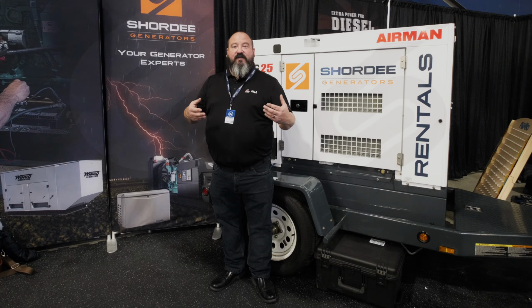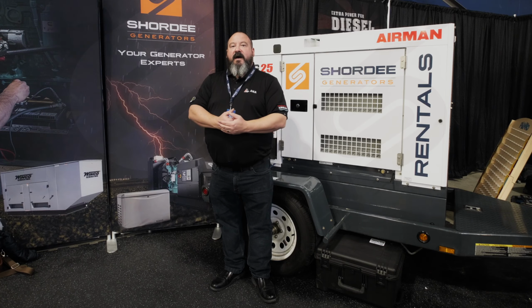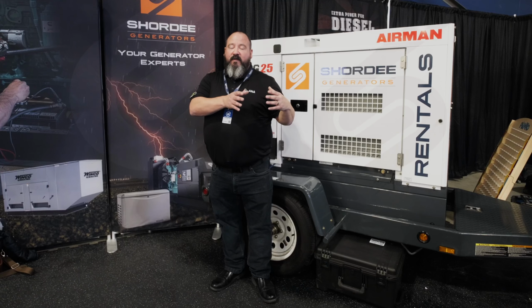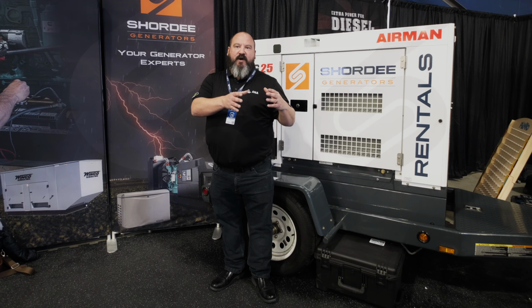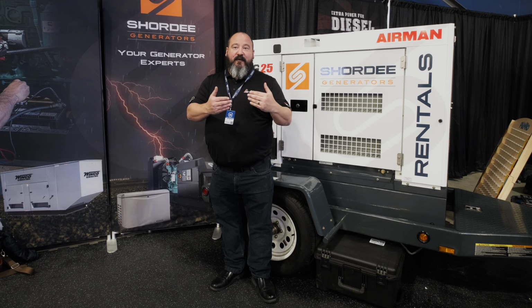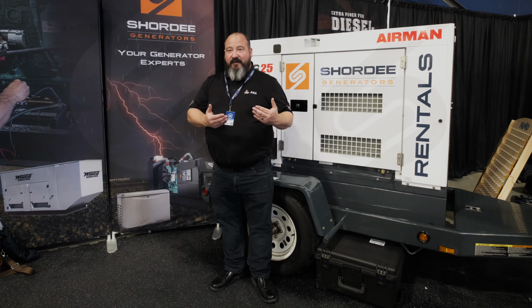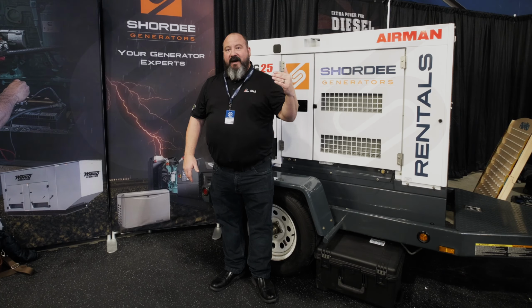Next thing it does is it reduces your fuel consumption dramatically. Generally what you're going to see is your average loads are going to be 3, 4, 5% load on the generator, maybe up to 20%. Your peak loads are where it takes it up to the peak. So the load will be running on battery 3 to 4 hours when sized properly. The generator will fire up, run for 45 minutes, and drastically reduce the amount of fuel, up to 80% reduction in fuel consumption. As the generator's not running, you're not burning that fuel. You're also eliminating a lot of the carbon footprint, the emissions coming off of the generator.